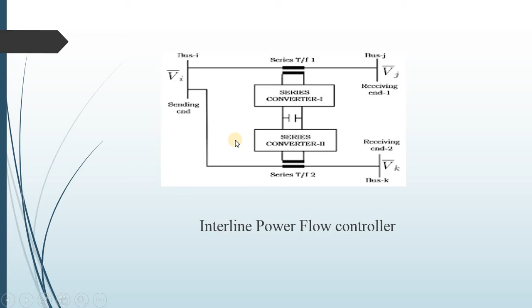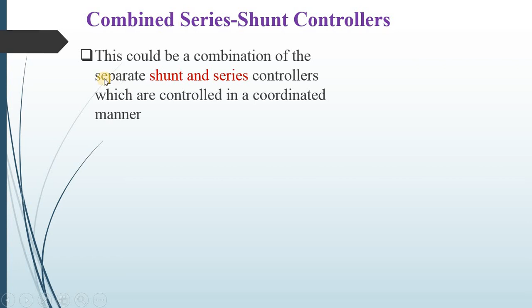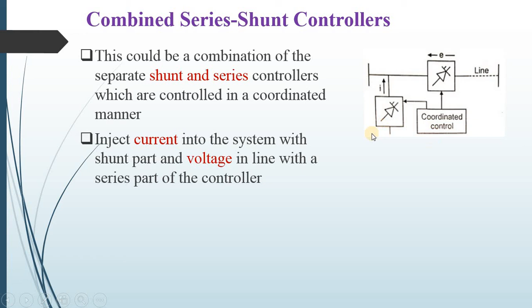Now let us see the combined series-shunt controller. In that, as the name suggests, one controller is shunt, parallel connected, and the second is series connected. So this could be a combination of separate shunt and series controllers which are controlled in a coordinated manner. The ones connected in shunt inject current into the system, and the ones connected in series inject voltage in the line as the series part of the controller. So this is the representation of the series-shunt controller; in that, one controller is connected in series and the second controller is connected in shunt, and these are controlled in a coordinated manner.